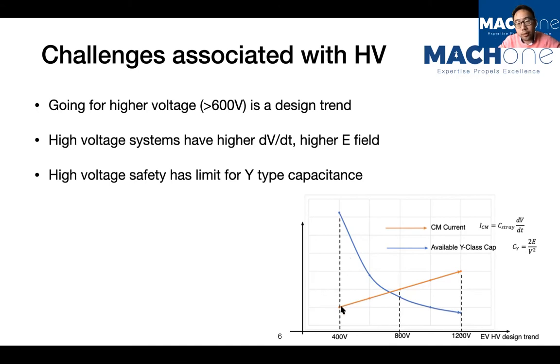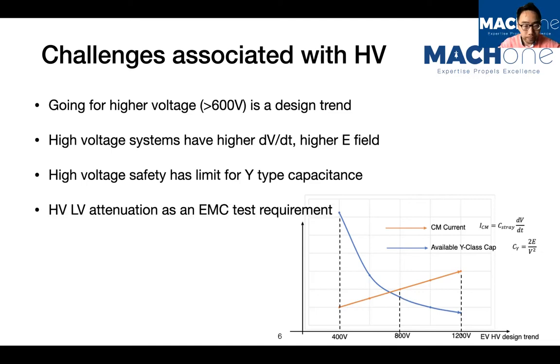Suppose you are designing a system and try to upgrade it from 400 volts to 800 volts. What does that mean for the common mode filtering capacitance you can use? You can only use 25% of the capacitance compared to the 400 volt system when doubling the voltage. So on one hand you have a much more challenging problem, a higher dV/dt, and on the other hand you're really limited by the filtering methods you can use. That's a big challenge.